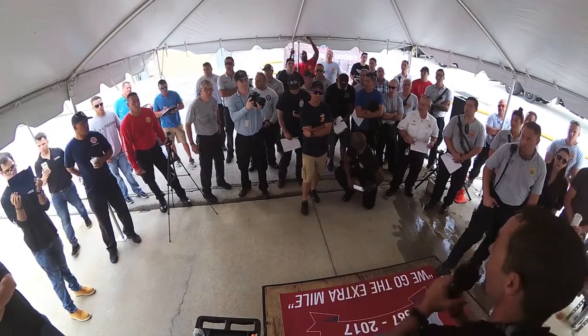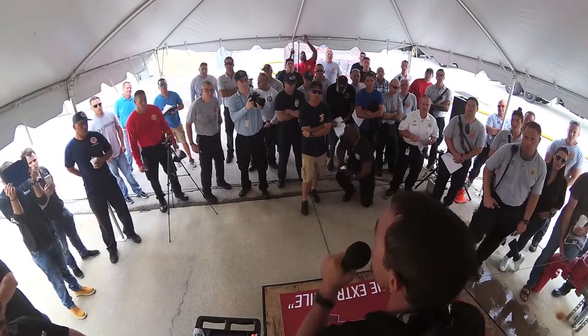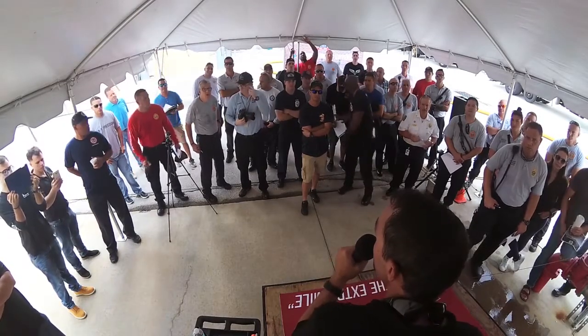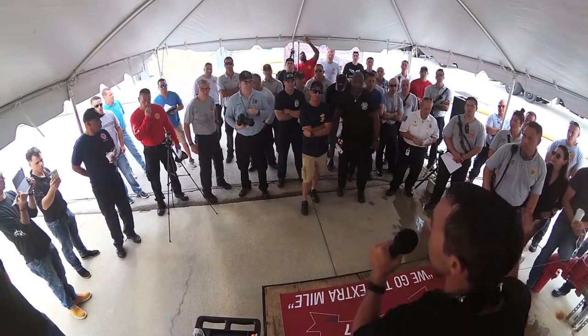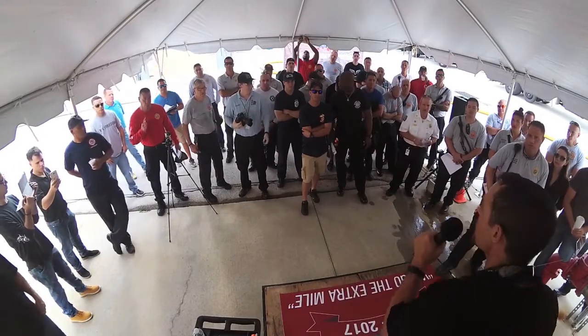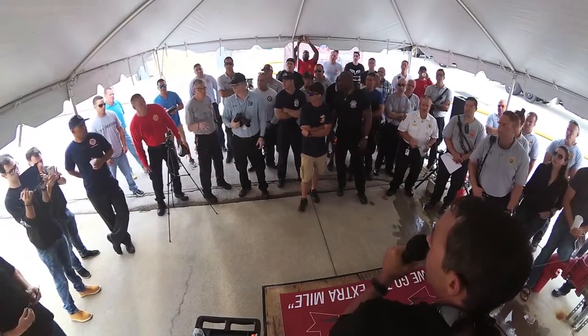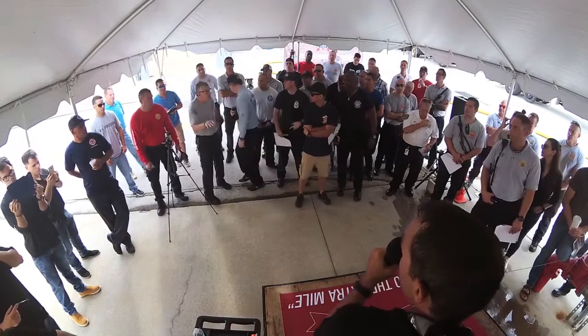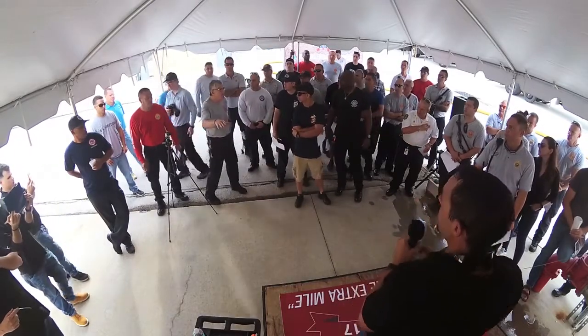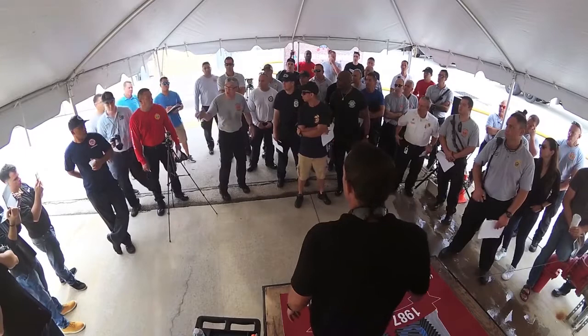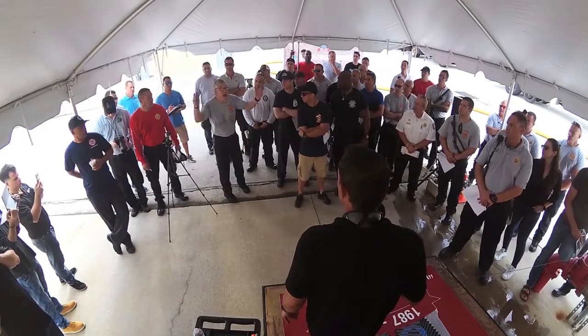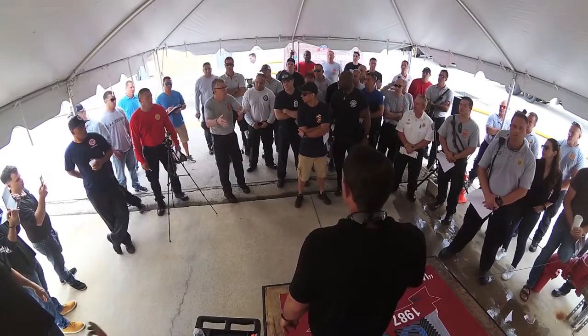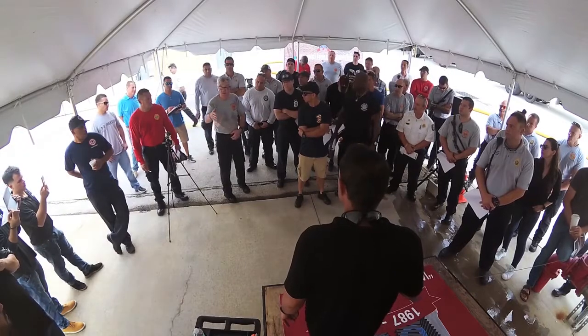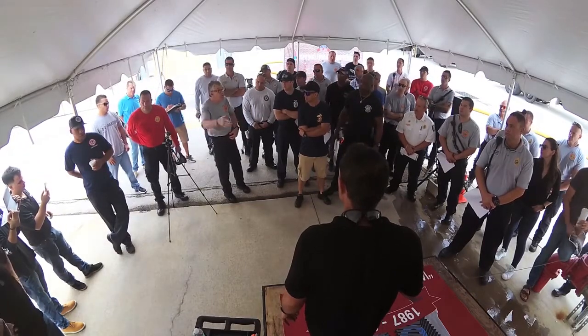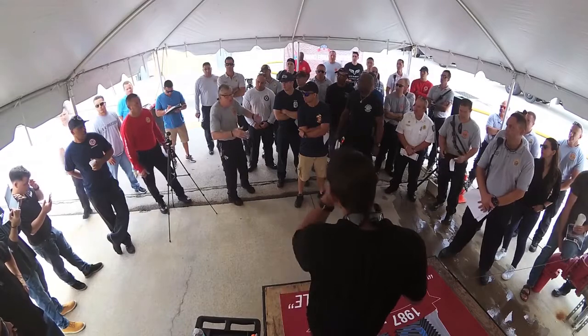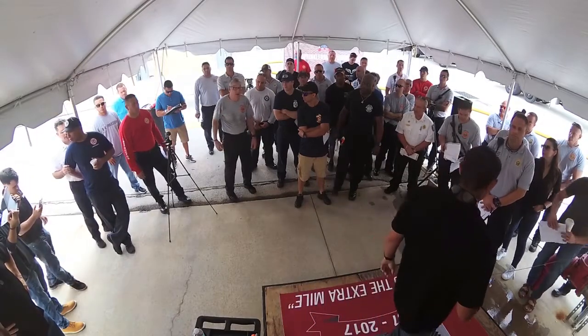All firefighters, okay. So you pull up to the building, do you guys send someone into the fire pump room? You should, yes. You should. So you come in, you hook up, you start getting water. One of the purposes of this class is we send somebody into the fire pump room. And it's like, okay, you were assigned the fire pump room. Now what? And part of the purpose of this class is that Greg, our pump guy, is going to explain what you would be looking for when you go in a fire pump.